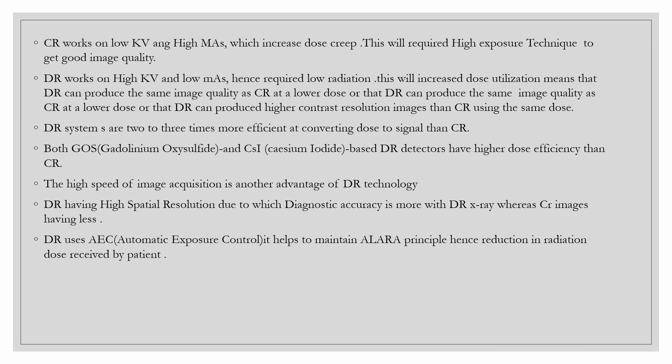In CR, the system works on low kV and high mAs, which increases dose creep and requires high exposure technique to get good image quality. In DR, the system works on high kV and low mAs, hence requiring lower radiation. This increases dose utilization, meaning DR can produce the same image quality as CR at a lower dose.